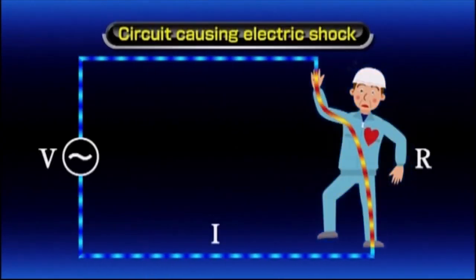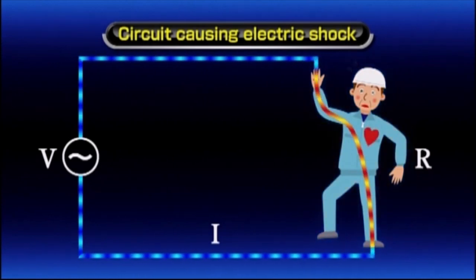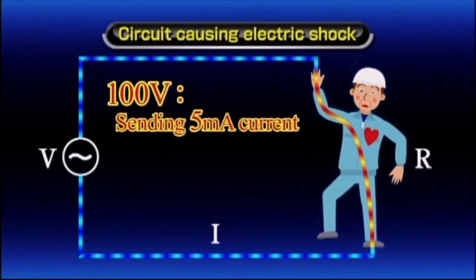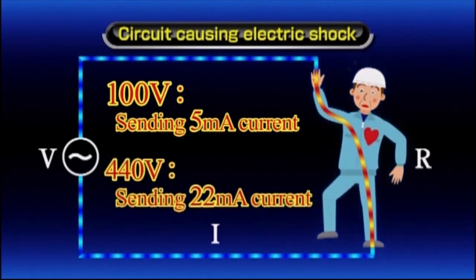The resistance of internal tissues remains almost unchanged — approximately 500 ohms for the area of the body between the hands and legs. Assuming dry skin offers a resistance of 20 kilo ohms, contact with 100 volts sends 5 milliamps through your body. Increase this to 440 volts and the current rises to 22 milliamps.